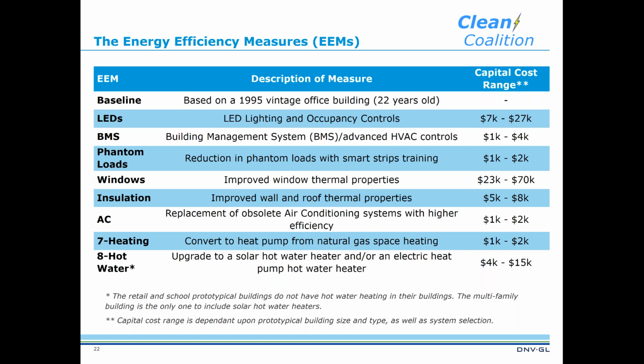As well as going low E, adding tinting. For insulation, we looked at blow-in insulation in most cases because in an existing building that's the least expensive option and gives you the most bang for your buck. For air conditioning, higher efficiency systems today, especially for these building sizes, are much higher efficiency than they were in 1995. For heating, we looked at converting to a heat pump in order to triple or quadruple our efficiency. And then for hot water, we looked at solar hot water as well as heat pump hot water systems.